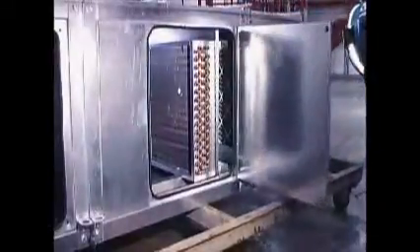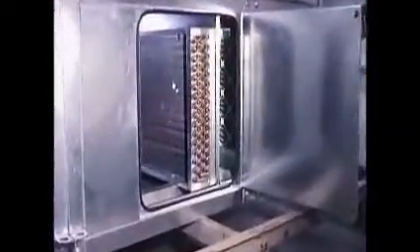After the damper, we need a heating coil in a temperate climate, anywhere up north, the Midwest, the Northeast. Now, remember, this unit is not a big unit compared to a recirculating unit. If the recirculating unit is 100% of the air that's circulated, this unit is only 20%. So we can afford to put the best preheat coil you can think of in there because it's a small coil. Downstream of the heating coil, we normally have the cooling coil. The cooling coil is a special coil.